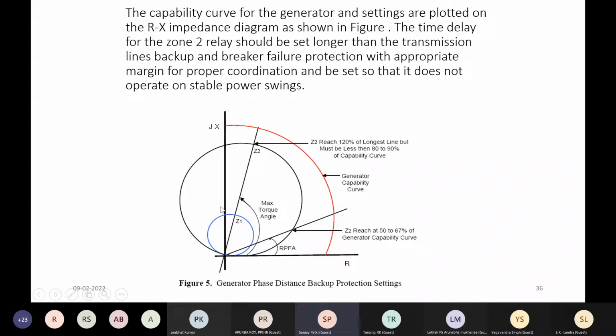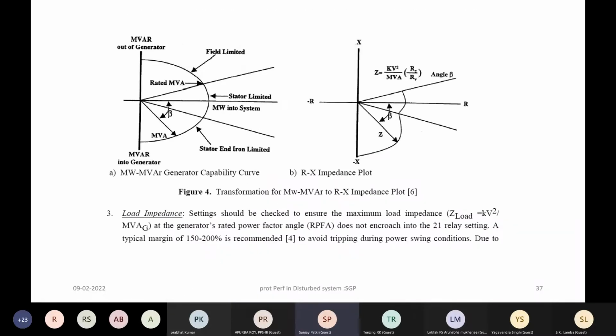This is what is illustrated in this diagram. You can see that this is your generator zone of the impedance relay. Then there is a generator and the transmission line, and then there is a load point. So there is a safe margin kept between zone 2 reach of the backup impedance relay and the load point, so that this load doesn't encroach into this zone 2 of the generator protection during power swing or any system disturbance. So that is one of the main important aspects of coordination.